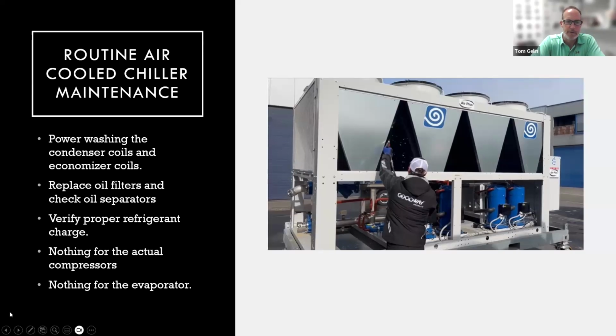I'm on the part that says nothing for the actual compressors as far as maintenance goes. I know a scroll compressor like the ones shown here, you can't really crack them open, so there isn't maintenance there. Yeah, there's nothing called maintenance for a compressor unless you have a full breakdown, but based on your oil analysis you'll know what you need to do. Sometimes you require full overhauling. Scrolls are usually replaced, I imagine, while screws and centrifugals you can service on site.